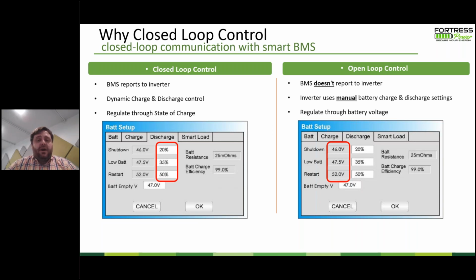What that means is even at a low state of charge, a lithium battery voltage is very stable. And that's why you can use the full range of the lithium battery, whereas you can't with a lead acid. If you're using that lead acid battery under full load, but it's only at a very low state of charge, you're not going to get enough sustained voltage to run your load. Whether that's an intense charge for a short period of time or a large, momentary load at the bottom of the state of charge, lead acid falls apart at heavy loads at low states of charge. The lithium maintains its voltage level even in those low state of charge conditions.